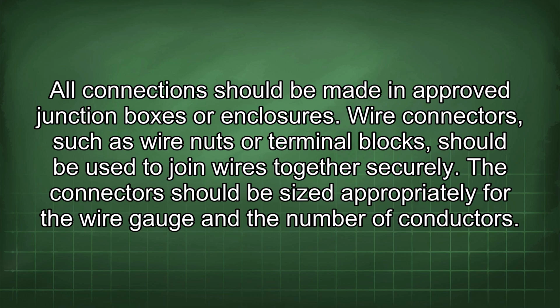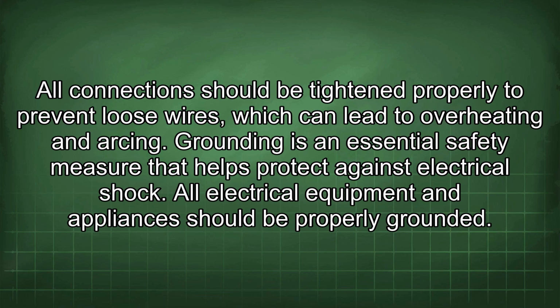All connections should be made in approved junction boxes or enclosures. Wire connectors, such as wire nuts or terminal blocks, should be used to join wires together securely. The connectors should be sized appropriately for the wire gauge and the number of conductors. All connections should be tightened properly to prevent loose wires, which can lead to overheating and arcing.